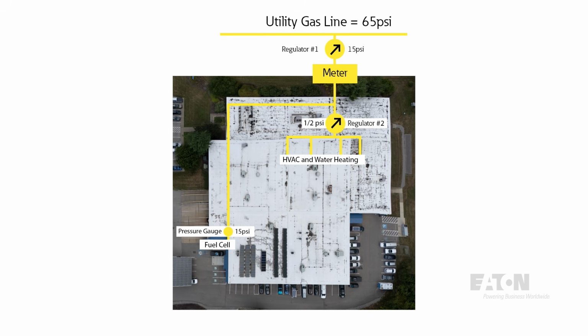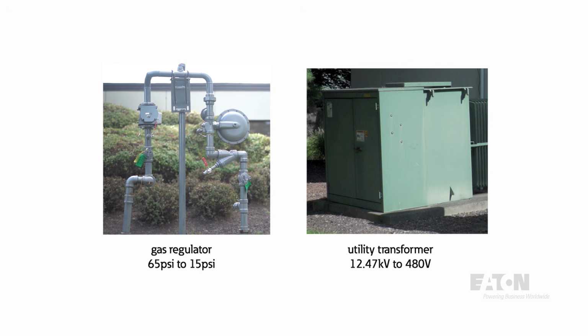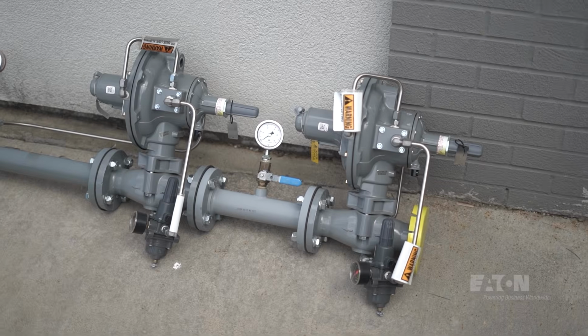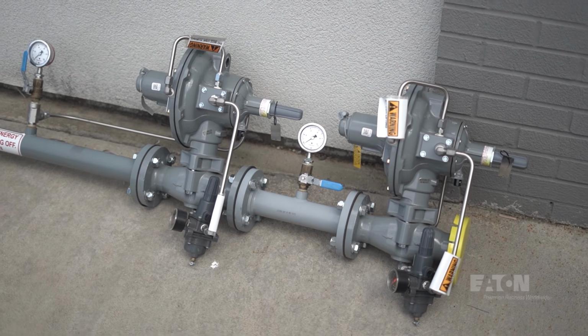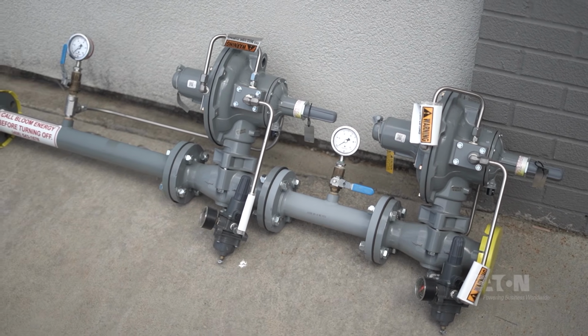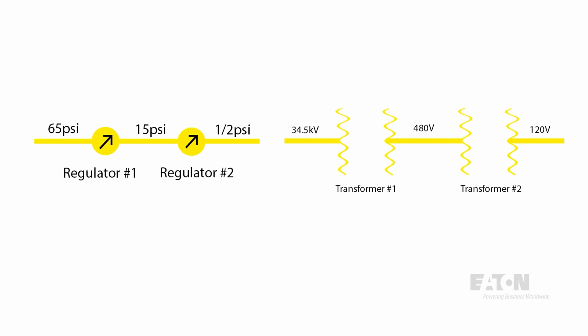Here's a drawing showing how our building is now fed to achieve the required 15 psi for the fuel cell. The interesting thing was the gas regulators stepping down the pressure are analogous to transformers stepping down voltage. In some cases, multiple regulators are required and placed in series to achieve this desired level. This is like stepping the voltage down from 34.5 kV to 480 with one transformer and then down to 120 with another. Bloom was very helpful working with us and the gas company since this was not something we're often involved with.